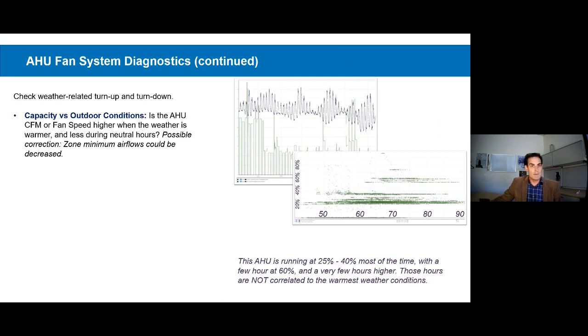Another thing to note here is that the highest number, the highest demand for fan power, does not occur at the hottest temperature. Again, as a design guy, the first time I saw this, my head exploded because I would have expected that the biggest number you ever see on this chart lines up with the 90 or 95 degree temperatures. But pretty much everywhere we've looked, that's usually not the case. That's also true with heating systems. The peak capacity rarely, if ever, occurs in the coldest hours of the year.